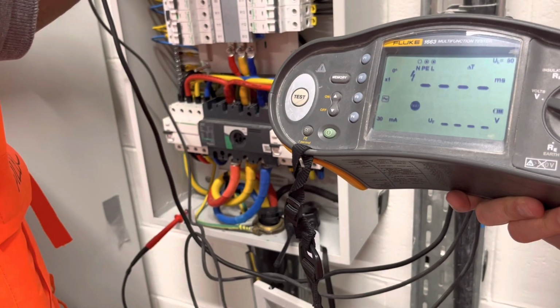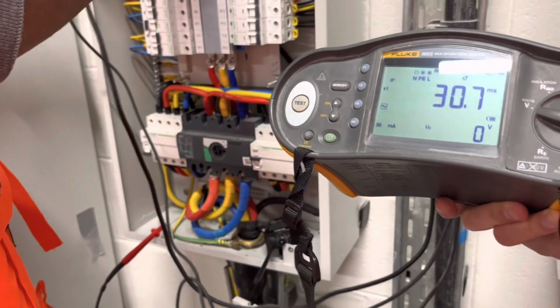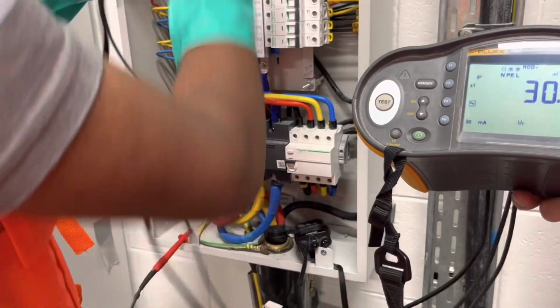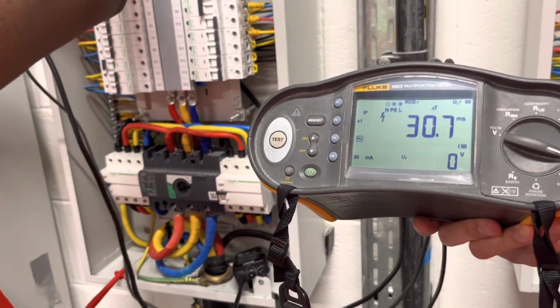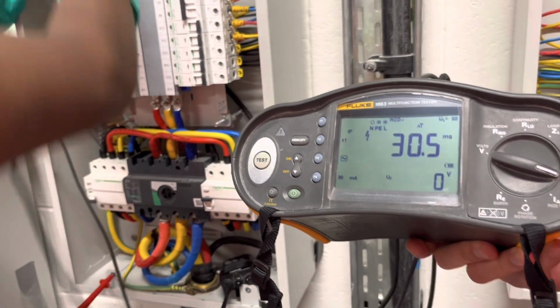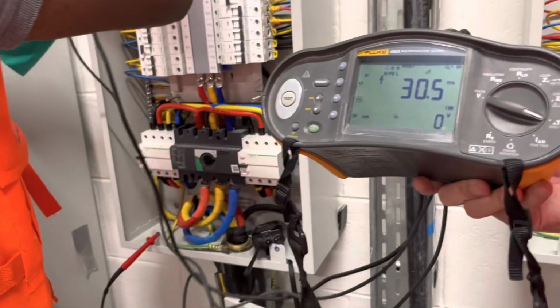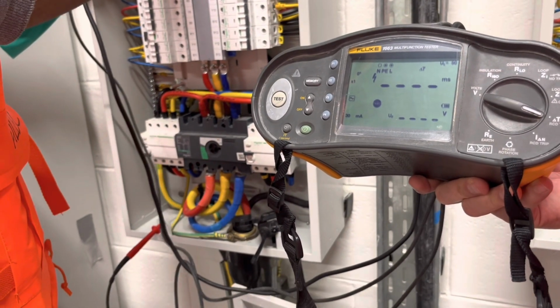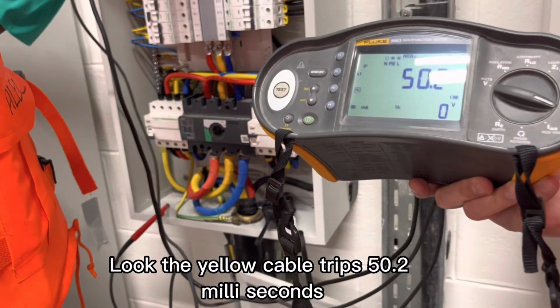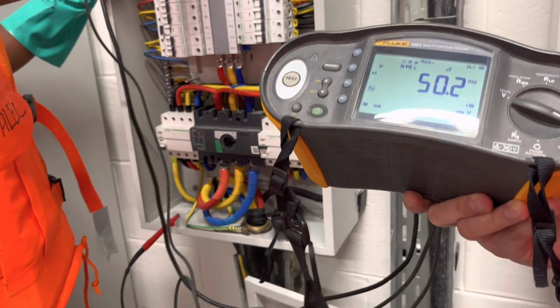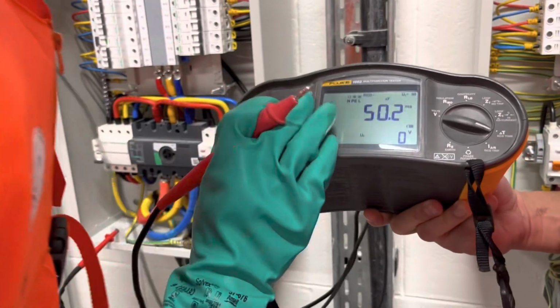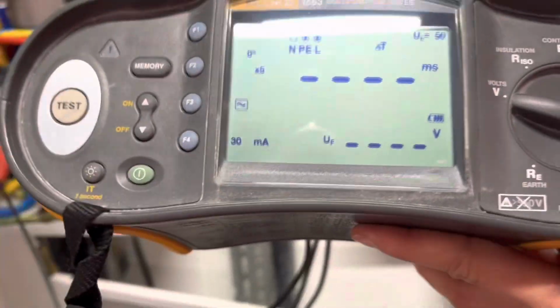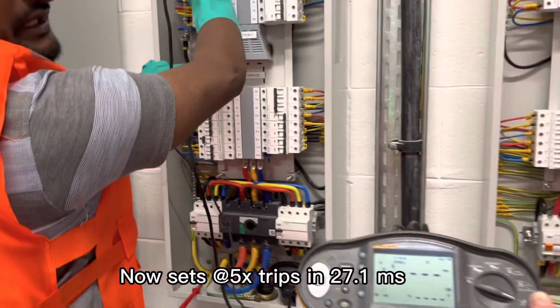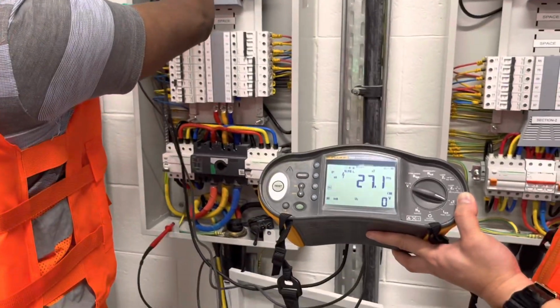Okay. 30 milliseconds, no? So the yellow one is rejected now. The blue one, the yellow? Okay, so what happened? 50, why 50? 50 milliseconds. Can you put it in 0.5? So this is times 5. Yes, times 5, and we will put also 1 up. Okay, the red one. Okay, trips at 27 milliseconds.